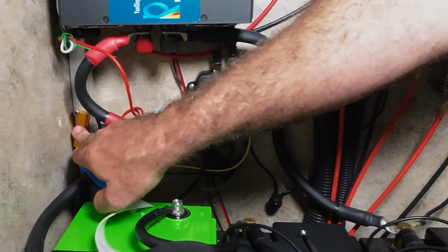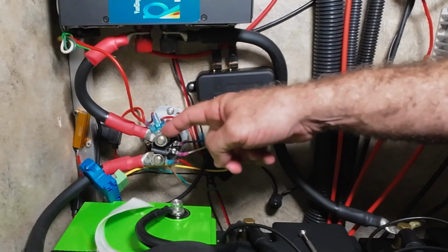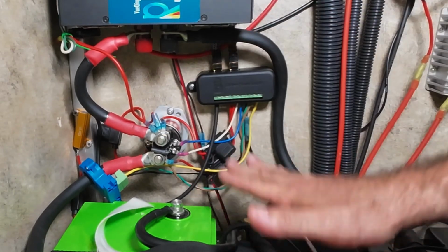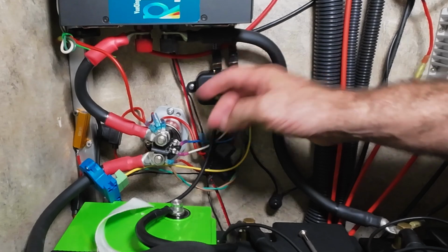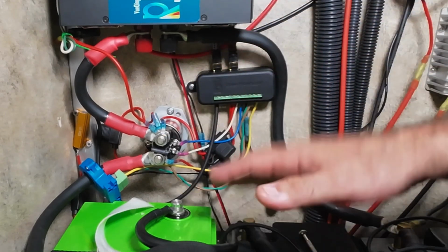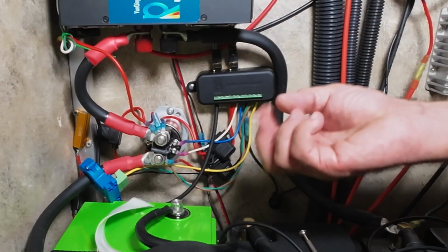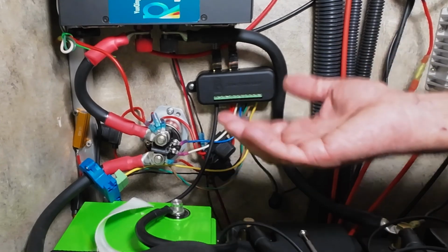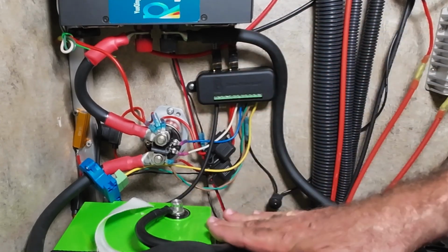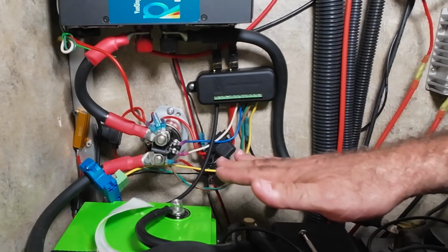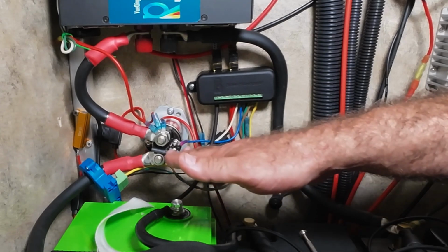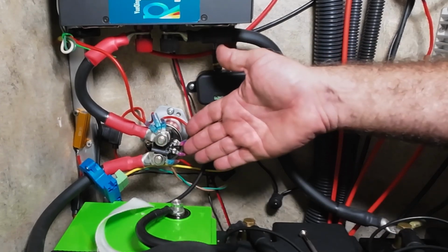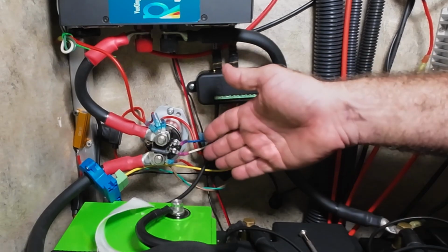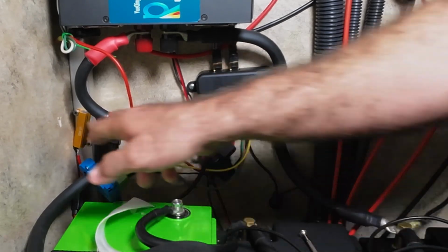Well, when you have that feature turned on, you have this installed, the BankManager will bring the batteries down to a lower voltage, which means the lead has to come down to a lower voltage before they reconnect. Kind of means your charge day is over, but more importantly, when you're down at that lower voltage, you're below the activation energy for that problem. So I can allow a little charge to come in - I don't have to keep turning off the contactor. So life is just generally better if you put that one in.